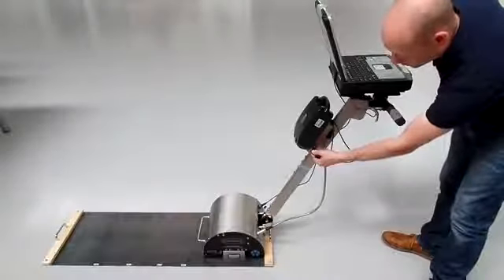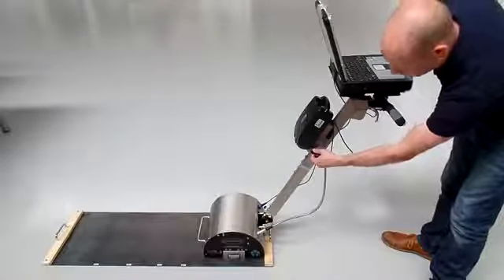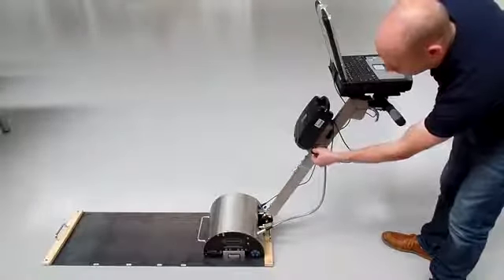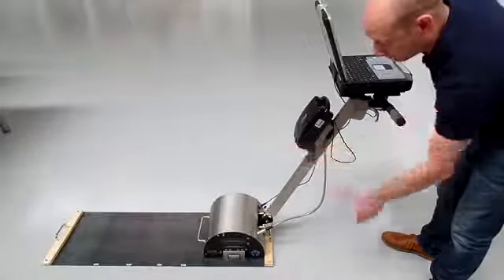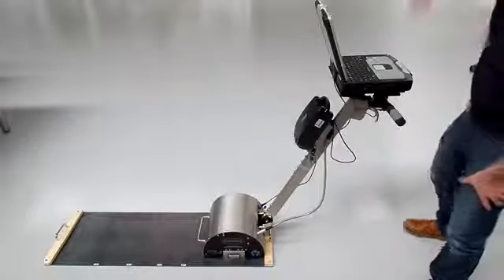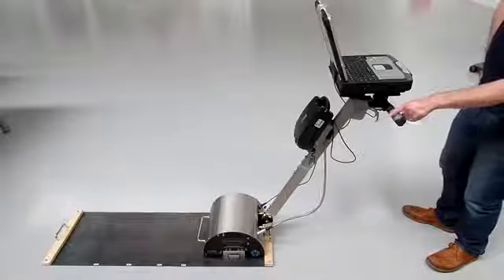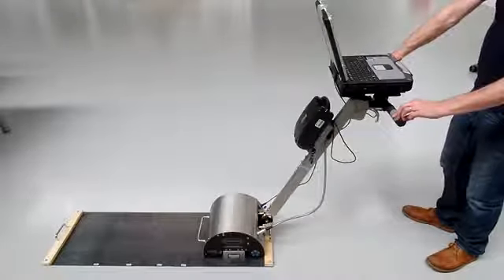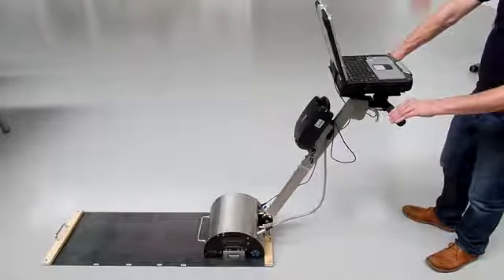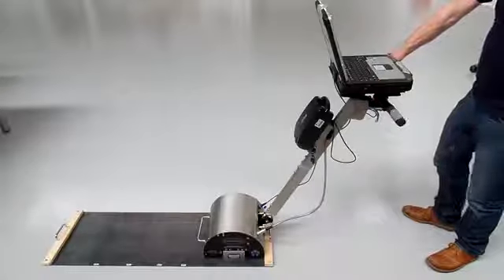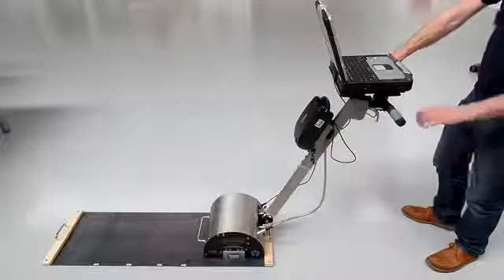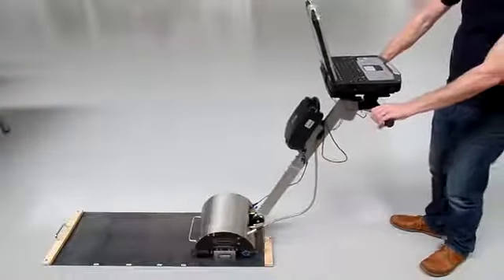The power key here is rotated all the way clockwise to ensure that power is supplied from the battery to the motors in the head unit. You will see that there is a lever here on the handlebars which, when you pull, engages the motor to allow you to drive the TruFlux over on the calibration plate, like so.